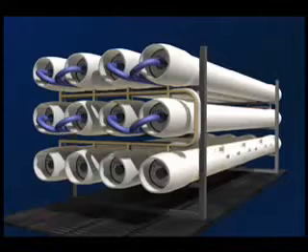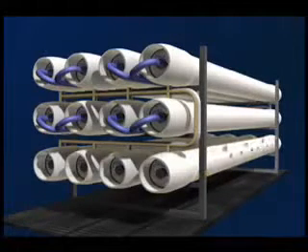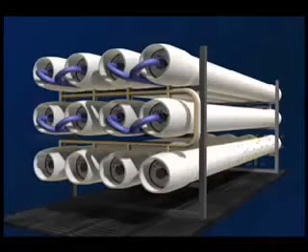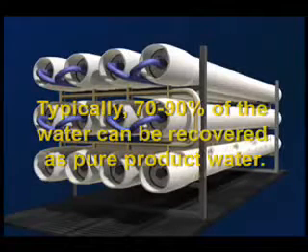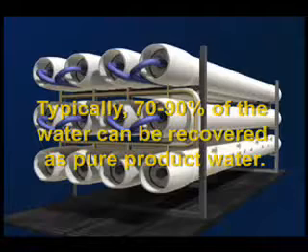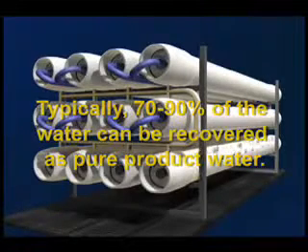The permeate water then flows out the end of the vessel and is collected as the product. And the reject, or concentrate, from that vessel may then flow through another vessel producing more permeate. The remaining concentrate may then be disposed of as waste or partially recycled as the feed. Typically, 70-90% of the water can be recovered as pure product.